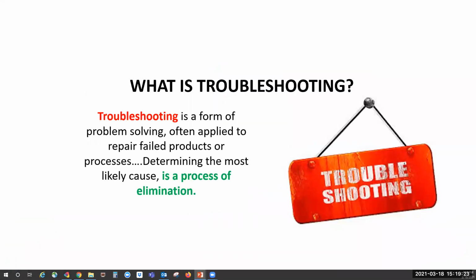Now we're going to get into some troubleshooting of the more common error codes we get. We're going to go over a few components operation, a couple tips when you're troubleshooting ductless systems. One, they do not operate like conventional systems. Two, do not immediately attach your refrigeration gauges to these systems. You can only tell if the system has refrigerant. You can't tell if it has the proper amount at this point. You always want to refer to your service manual for detailed troubleshooting on all error codes.